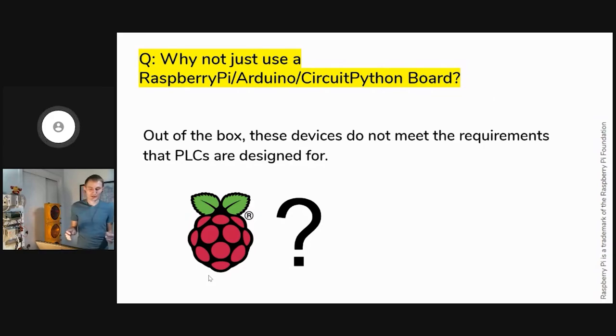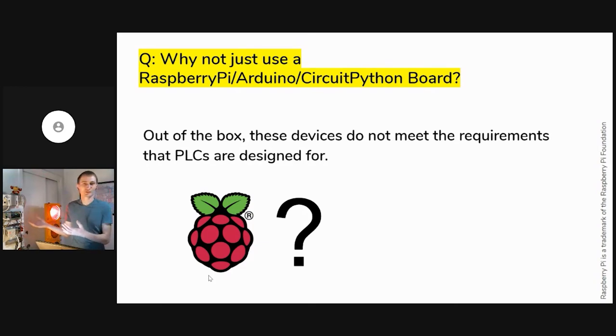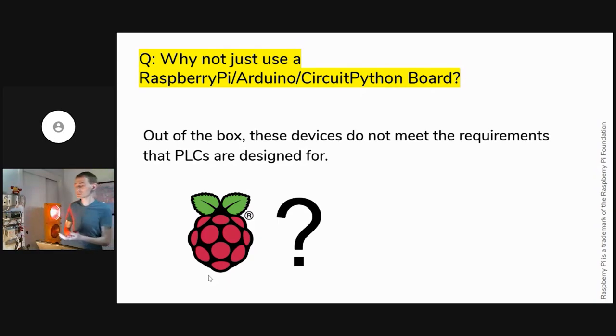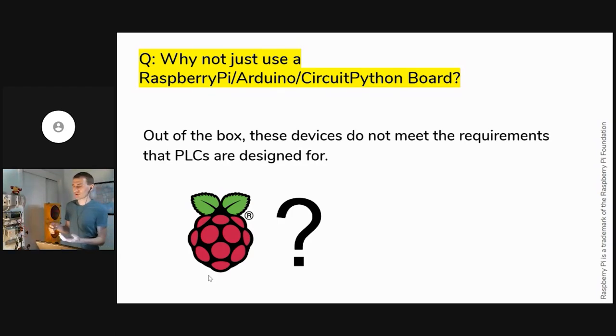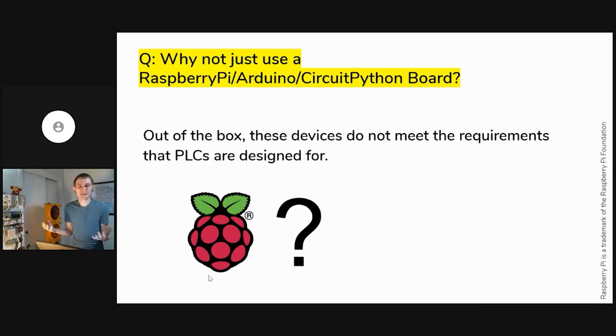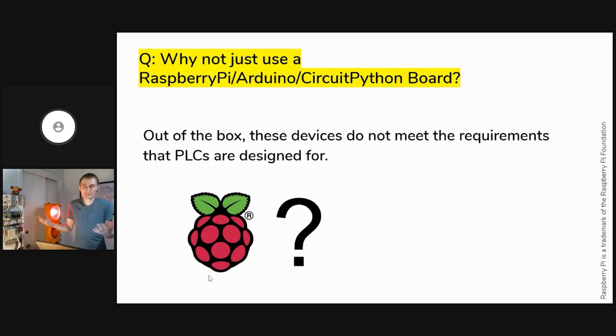Another question: why can't we just use a Raspberry Pi? A Raspberry Pi can do blinking lights, but out-of-the-box devices like it don't meet the requirements PLCs are designed for: real-time code execution, survival in extreme temperatures or humidity, and resistance to electromagnetic interference common in factories. You can modify a Raspberry Pi to meet those criteria, but then it looks like a PLC and costs as much. So if your requirements warrant a PLC, you need a PLC; if they don't, you don't.